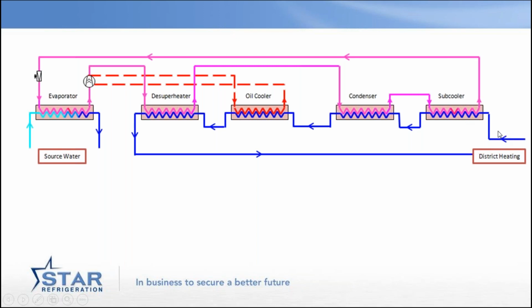The subcooler is an interesting one because the cooler the water comes back from district heating, the more subcooling you can do. And that varies by about 0.5% per degree that the delta is wider. So district heating at, let's say, 80-60 will have an efficiency, but 80-50 will be 10 Kelvin times 0.5% better, so 5% better just by managing the district heating temperature. And that's where optimization of district heating is really, really critical. Equally, changing from 80 to 75 and lowering the condensing temperature affects the performance by about 1.5% per Kelvin. So changing from 80-60 to 75-45, for example, would give you probably well over 25% improvement in the performance.